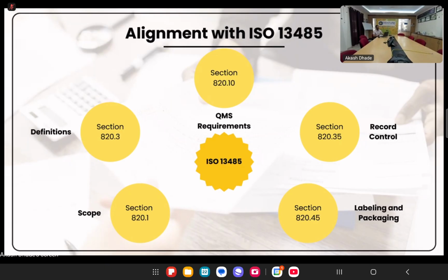Then it also talks about foreign manufacturers, what their requirements are. So if you are familiar with 21 CFR 820, the QMSR also speaks the same scope for foreign manufacturers. Okay, so different entities as I mentioned, design and development entities, packaging entities, manufacturers, all these are under scope of QMSR. So this section, which was aligning with QSR, is also the same for QMSR, but more aligned with ISO 13485. ISO 13485 also has certain requirements for manufacturers. So if you are a manufacturer which fits the definition given by this scope, then in line with that, you should also fulfill the requirements of ISO 13485.